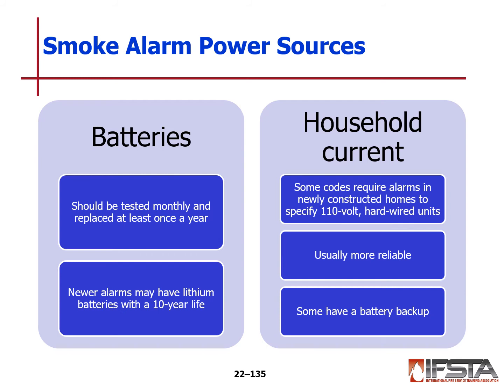Power sources for our smoke alarms can be regular household current, and they can be battery operated or both. A lot of detectors in the home in new construction are required to be on household current with a battery backup. So if the power does fail, these alarms will still operate. With batteries, they should be tested every month and replaced once a year. Newer alarms may have what's known as the lithium battery, and these do have a 10-year shelf life. And there is printing and stickers on the detector itself that lets us know that it has a 10-year battery.